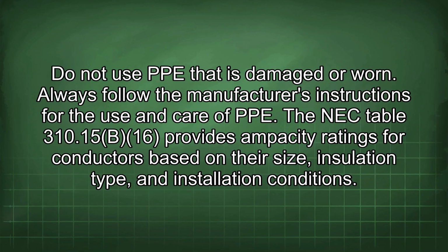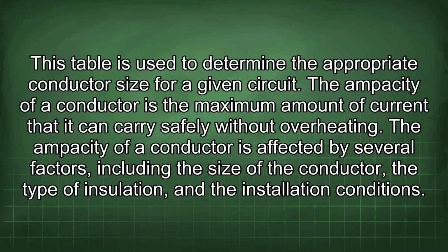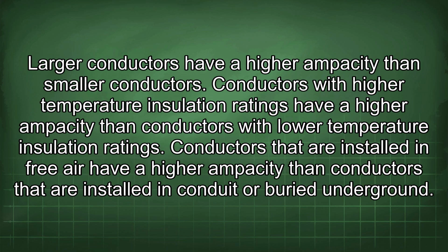The NEC Table 310.15(B)(16) provides ampacity ratings for conductors based on their size, insulation type, and installation conditions. This table is used to determine the appropriate conductor size for a given circuit. The ampacity of a conductor is the maximum amount of current that it can carry safely without overheating. The ampacity of a conductor is affected by several factors, including the size of the conductor, the type of insulation, and the installation conditions. Larger conductors have a higher ampacity than smaller conductors.